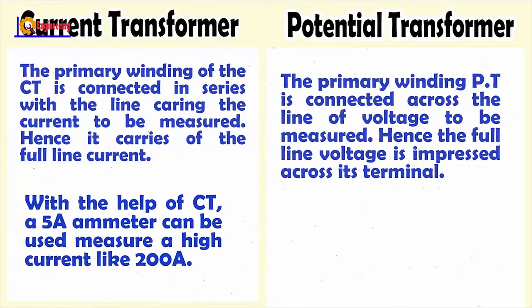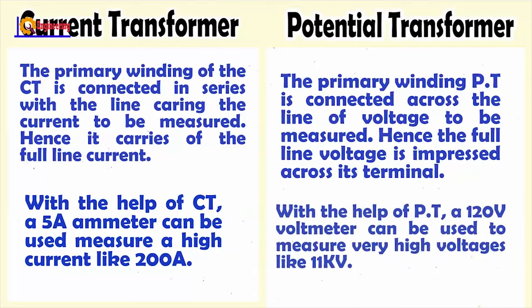With the help of a current transformer, a 5A ammeter can be used to measure a high current like 200A. With the help of a potential transformer, a 120V voltmeter can be used to measure very high voltages like 11kV.